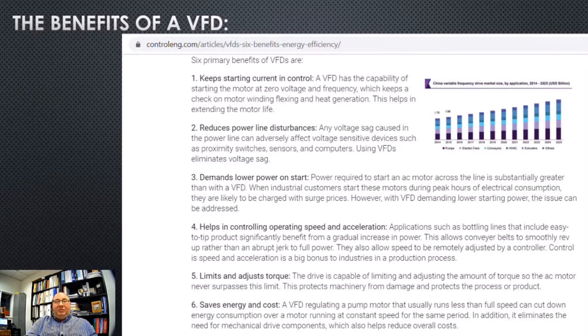So we could keep the starting current in control, reduces the power line disturbances, demands lower power on startup. It helps in controlling operating speed and acceleration. All right, it limits it and adjusts the torque, which is pretty neat.